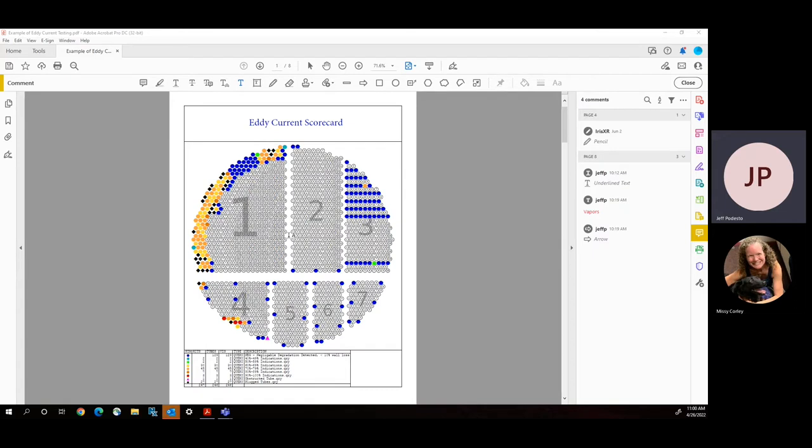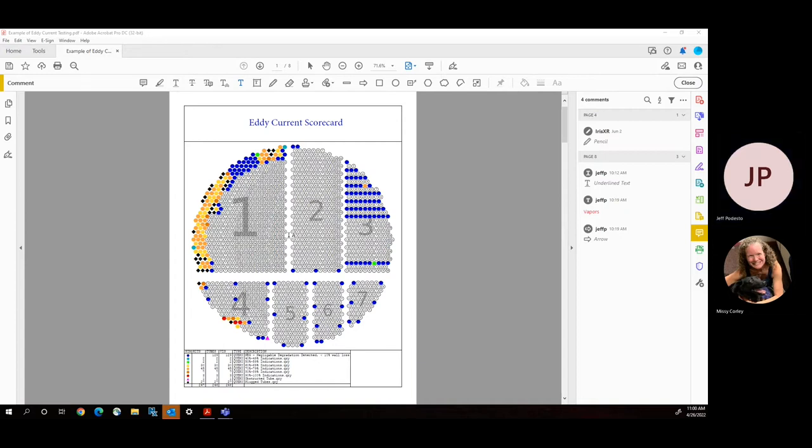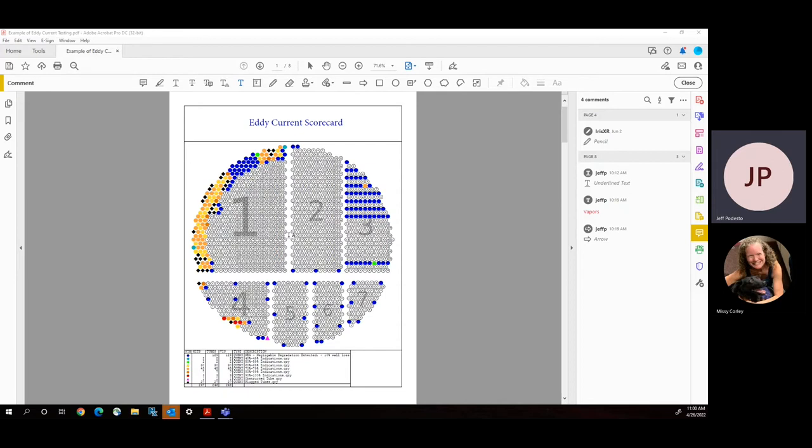And we're trying to come up with solutions to provide us information to allow us to do reasonable repairs to these evaporators. What you're seeing on the screen right now is an eddy current scorecard. Basically, this is the byproduct of testing with an eddy current system. That's looking down on the top of an evaporator that has about 1,500 tubes. And a quick analysis would be to tell you that the blue dots are good tubes, the red dots are bad tubes, and the colors in between represent tubes that have some level of degradation and help us determine what's going on in the evaporator.